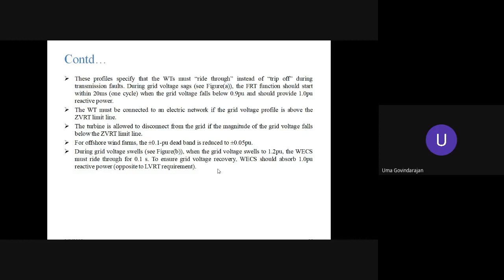So during grid voltage sags, the FRT functions should start within 20 milliseconds, within one cycle, when the grid voltage falls below 0.9 per unit, and should provide 1 per unit reactive power. So even during the grid faults, apart from the generation, support of the reactive power is very, very essential during this ride-through condition.